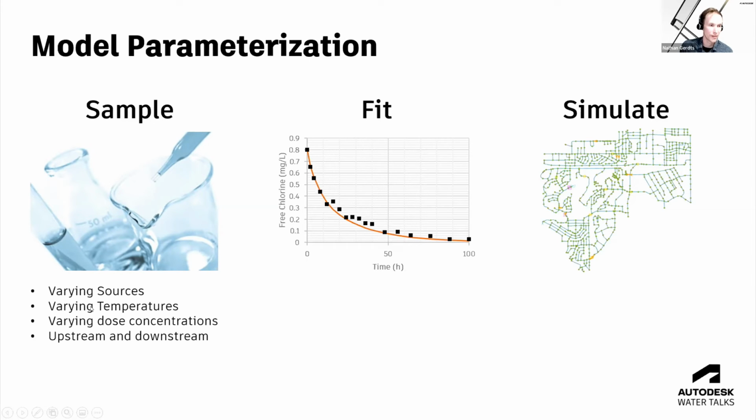If you want to account for varying temperatures and have that dynamic flexibility down the road, get samples at varying temperatures, and then you can calibrate that EOR coefficient. Also, if you can, get varying initial conditions on the chlorine concentration. And these ones will be your lab bulk samples to get the bulk decay, but also, of course, get some downstream concentrations to validate your model and do the pipe wall reaction coefficients.